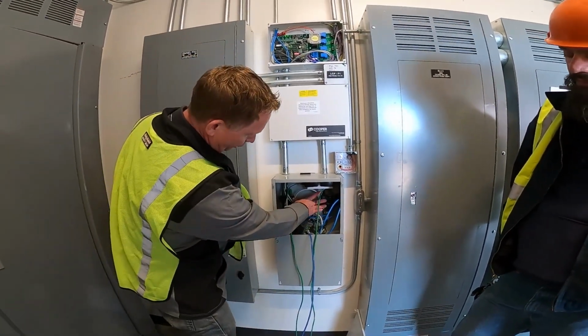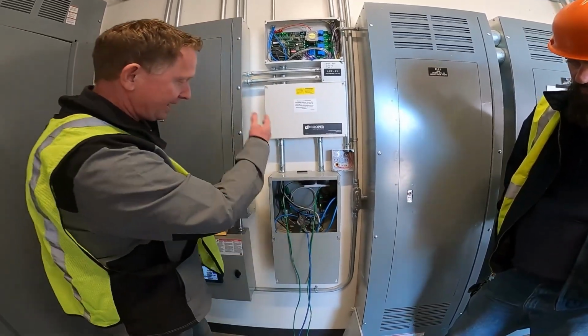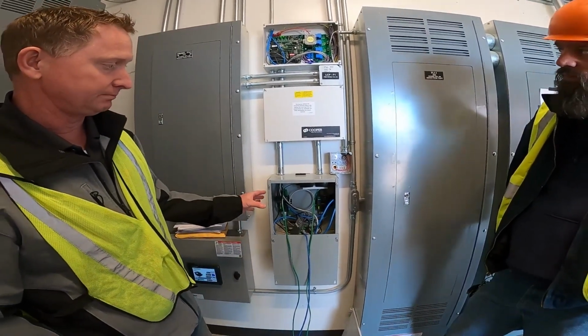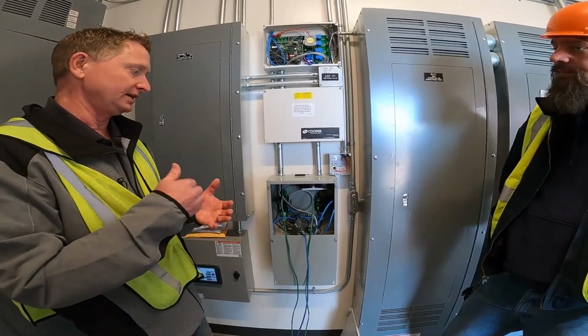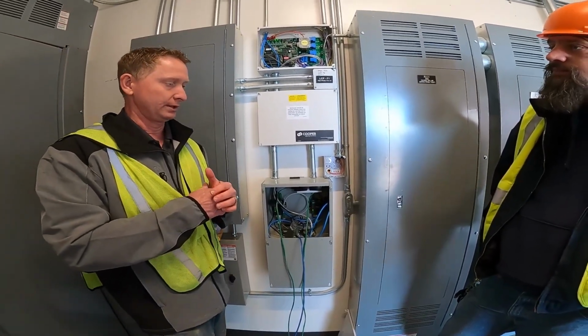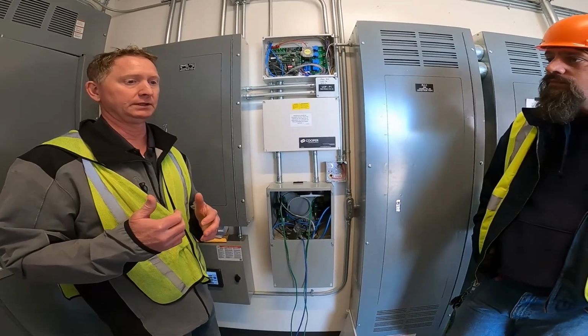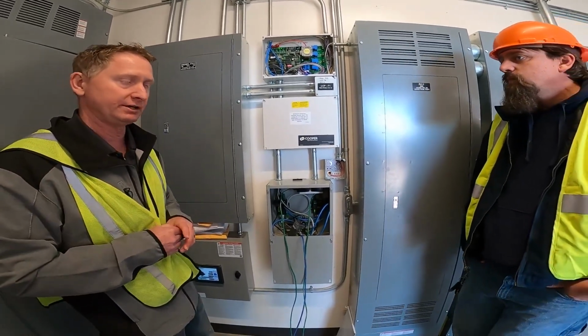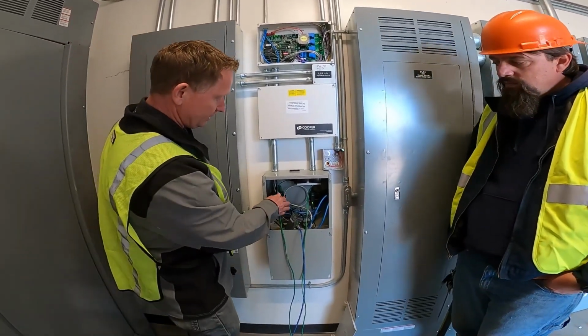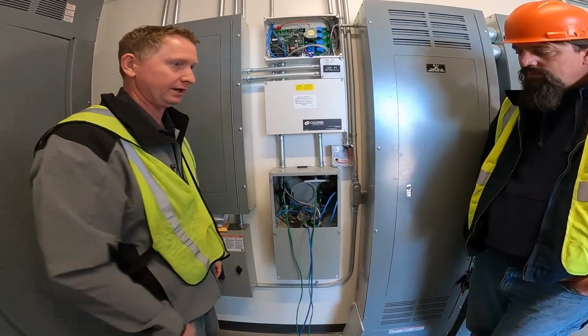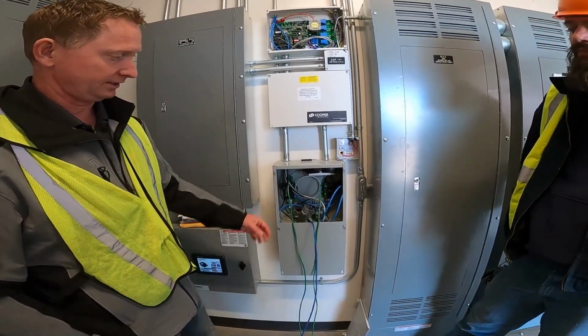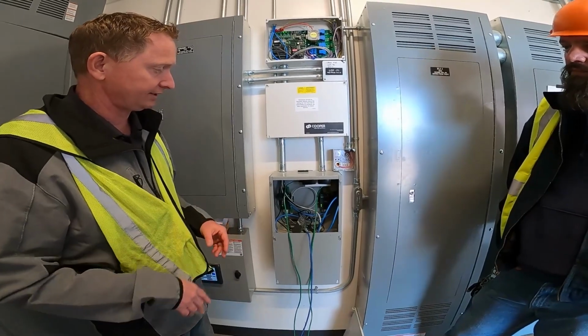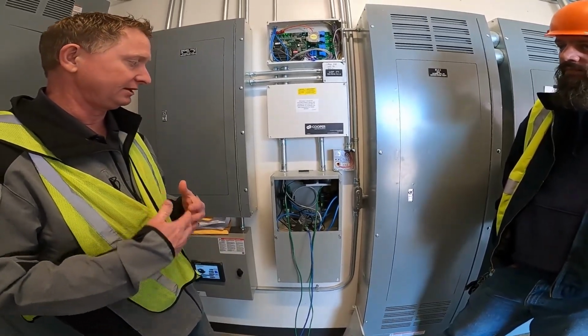And then these 2 are what's going to communicate back into the system, so you have 2 of them. One of them you can communicate in with your laptop onto the network for programming, and the other one's going to be dedicated for your BMS system, your BACnet system. Because if you do them both together, there's going to be interference.